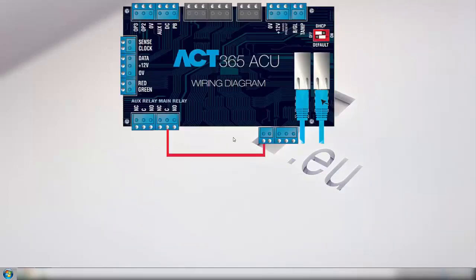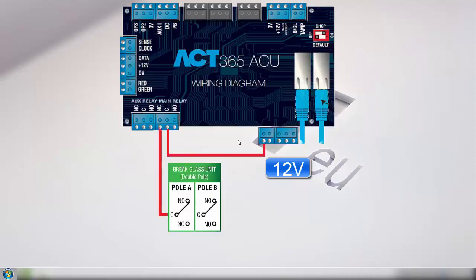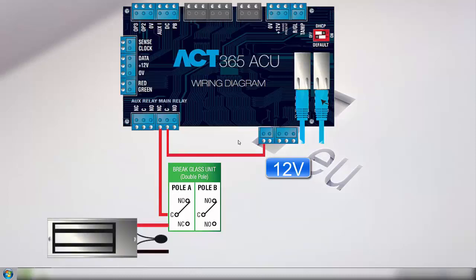In order to wire the mag lock we need to take 12 volts from the 12 volt output and wire it into common on the main relay. We then have to wire from normally closed on our relay to common on our break glass unit. Then from the normally closed on the break glass unit to the positive of the mag lock. Lastly to complete the circuit we have to connect a negative of the lock back to 0V on the PSU.